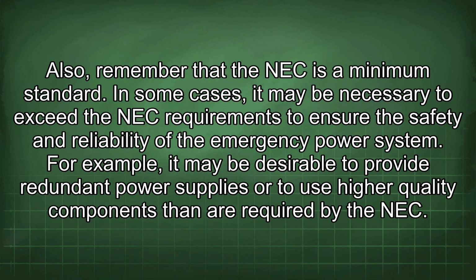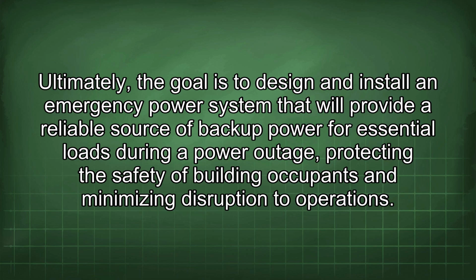Also, remember that the NEC is a minimum standard. In some cases, it may be necessary to exceed the NEC requirements to ensure the safety and reliability of the emergency power system. For example, it may be desirable to provide redundant power supplies or to use higher quality components than are required by the NEC. Ultimately, the goal is to design and install an emergency power system that will provide a reliable source of backup power for essential loads during a power outage, protecting the safety of building occupants and minimizing disruption to operations.